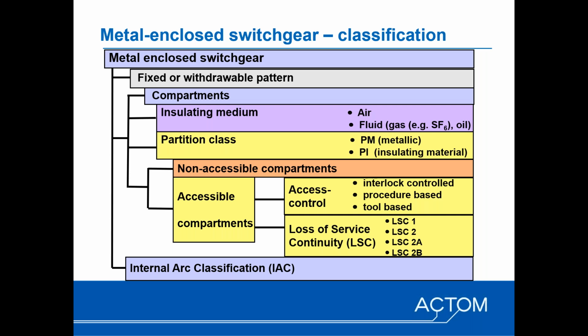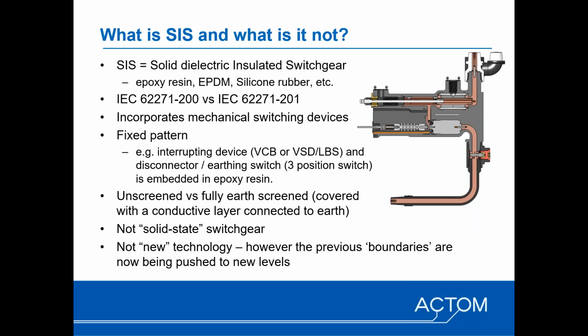Then there's important concept within medium voltage switchgear assemblies, and that relates to the loss of service continuity, and there's 4 different categories that are covered. We won't go into detail in that, but we'll just mention what's relevant insofar as fixed pattern solid dielectric switchgear is concerned. And then, of course, the access to the different compartments, specifically the accessible compartments, is also covered in the standards, and all these concepts were introduced in the 62271 series. And then, of course, finally, internal arc classification. Okay, so moving on to the details.